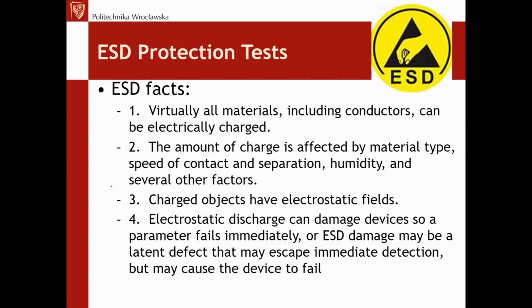Okay, let's go further. The fourth group that I think is important during the R&D phase, during the development of any new device, is testing for protection against ESD, so electrostatic discharge. Again, this is kind of a reliability test, but it's a broader category. That's why I didn't place it into the reliability test category, but as a separate test, because this category is very broad, very wide. ESD, electrostatic discharge, is a very common phenomenon.